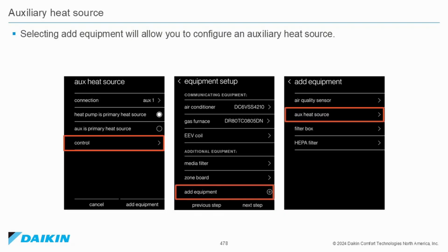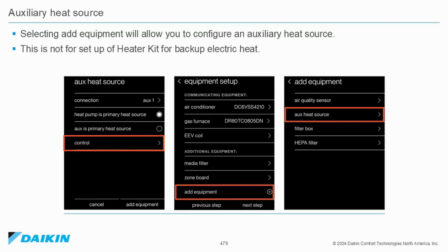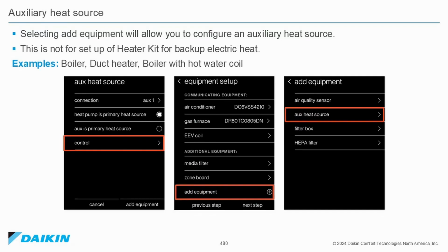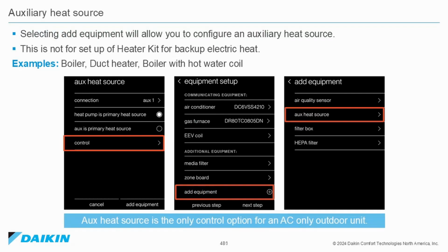Auxiliary heat source. Selecting Add Equipment will allow you to configure an auxiliary heat source. This is not for setup of a heater kit for backup electric heat. This would be for boiler, duct heater, boiler with hot water coil. Auxiliary heat source is the only control option for an AC-only outdoor unit.